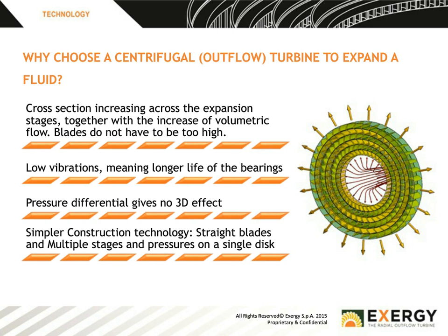It's also the same as a steam turbine. A steam turbine is usually an axial turbine. So again, we have this very good expansion ratio on this type of design. We also have, which I'll get to the reasons in a minute, low vibrations. We have a very good pressure differential across the disc as this fluid moves outwards. And we have a very simple construction. Because the tip speed is the same, the blades actually are straight, which you'll see again on another slide.